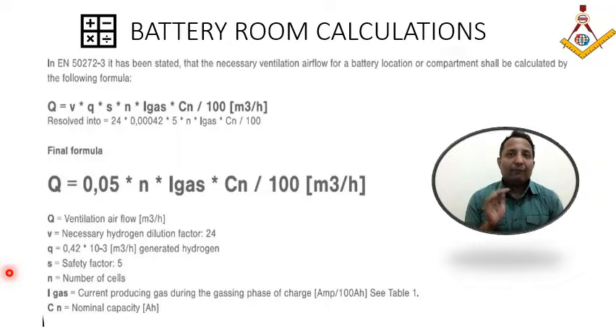And when we talk about the requirement of air conditioned air, when we supply it to this battery room, it is always supplied at the floor level. So a draft effect should happen. So gas should get pushed to the level above the ceiling. So that is a requirement. So ideally it should get sucked properly.